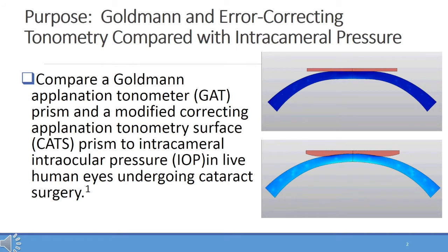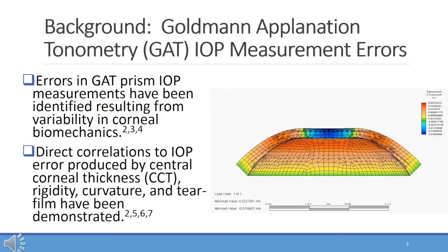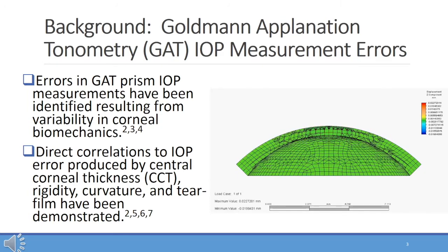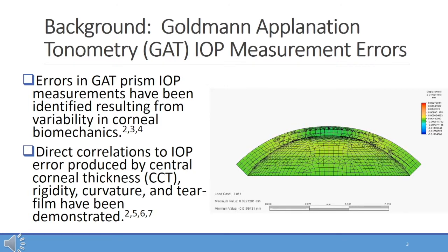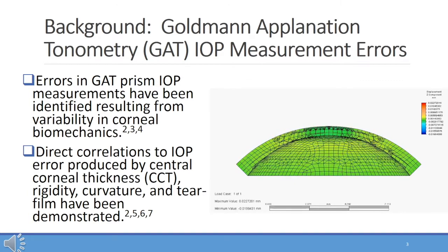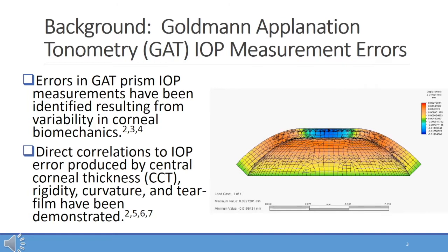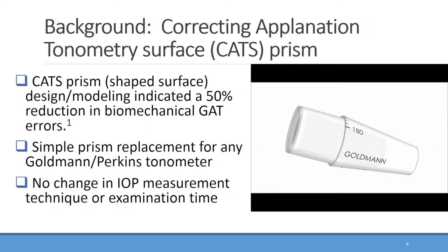The purpose of the study is to evaluate a correcting applanation tonometry surface prism, or CATS prism, and the reference tonometer GAT prism, compared to a true gold standard of transducer-measured intracameral pressure in live human eyes. It has been demonstrated over many decades of publications, and even mentioned by Goldmann himself 60 years ago, that several IOP measurement errors are present. Those errors include corneal biomechanical errors of central corneal thickness, corneal rigidity, corneal curvature, and separately the corneal tear film adhesion force.